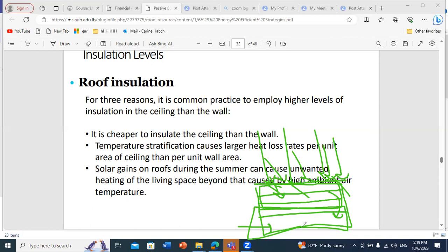So by this effect, you are causing a higher stratification, and this high stratification created within your space will lead to a high temperature difference between the upper zone and the lower zone, which will lead to a warm-up even of the occupied zone, and this is not desired. Okay, and this will lead to a high heat loss rate per unit area of the ceiling, because if we are talking about summer, you will have overheating, and in winter, you have heat losses from the roof because of the stratification of temperatures in the vertical direction.